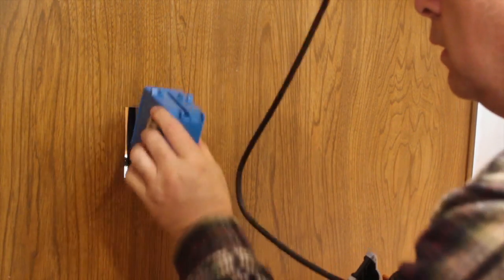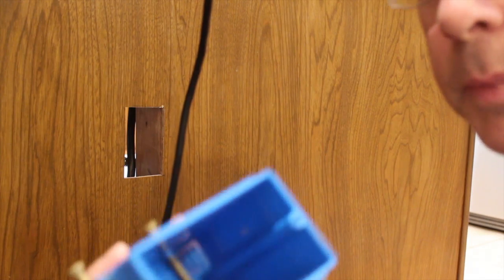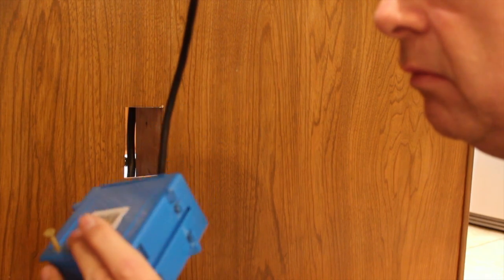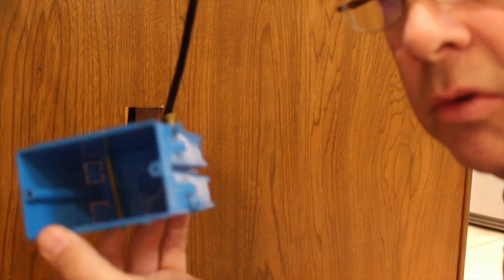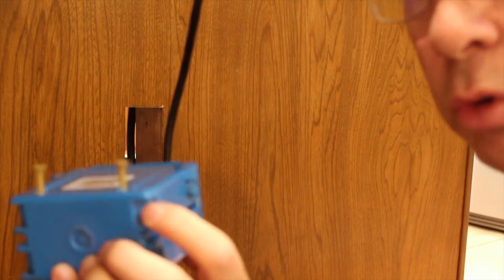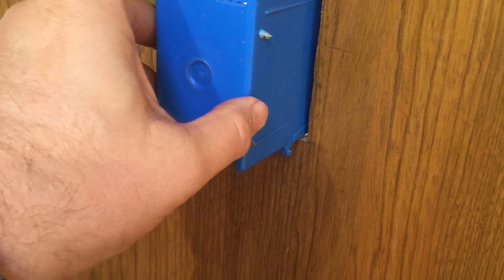So there's the hole. The box is good. These kinds of boxes come with nails that are inserted through these diagonal slots. I didn't want to have to swing a hammer back there, so I took a couple of three-inch screws and ran those through the inside. They're far enough away from where the Romex goes that they won't conflict, but it allowed me to be in there with my impact driver and a T25 head and be able to securely attach it to the stud. Let's reset the camera and go do that right now.